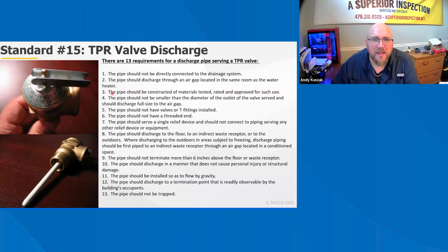Well, yeah, number 2, I just hit on that. Number 3, the pipe should be constructed of materials tested, rated, and approved for such use. So on this, you're going to find all kinds of materials. I've seen water hoses used for discharge lines. You'll find a lot of times, and I don't know how or why this became common, but I've seen it a lot on older homes, with a 20-year-old water heater, where you'll have the discharge, the temperature pressure relief, the TPR valve, which for the life of me, I think it's 1.5 inches.